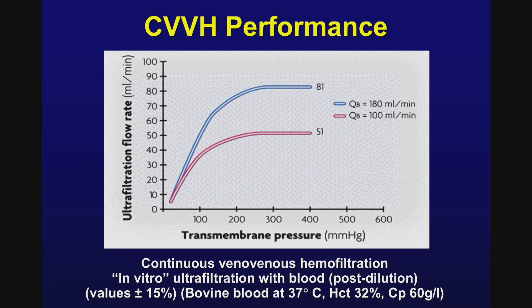This graph shows ultrafiltration flow rate on the y-axis and transmembrane pressure on the x-axis. The blue curve represents a blood flow of 180 mL per minute; the red curve represents 100 mL per minute. As transmembrane pressure increases, the ultrafiltration rate increases, but begins to plateau at around 200 to 250 mmHg. By increasing blood flow by 80 mL per minute up to 180 mL per minute, the ultrafiltration rate can be increased dramatically — from about 40 to 50 mL per minute up to about 80 mL per minute.